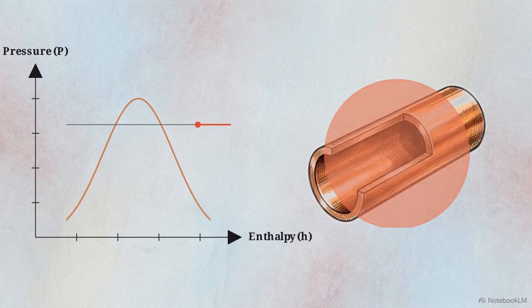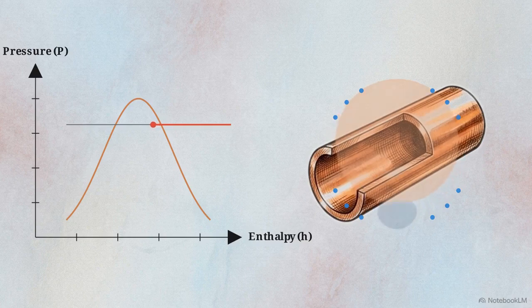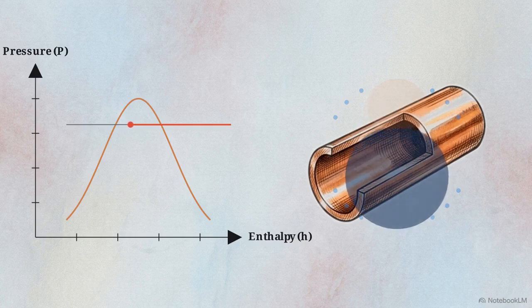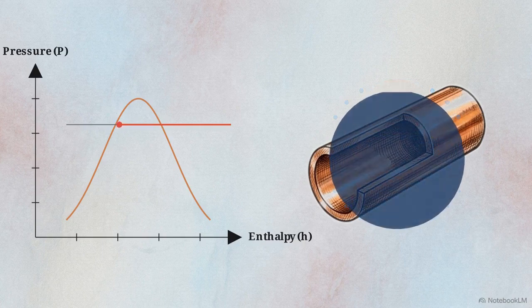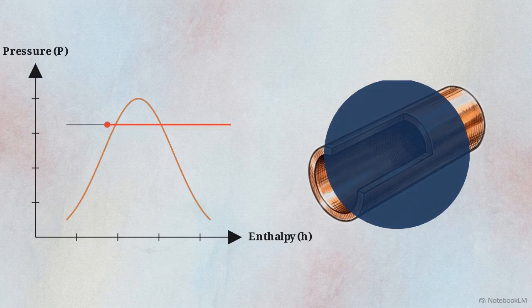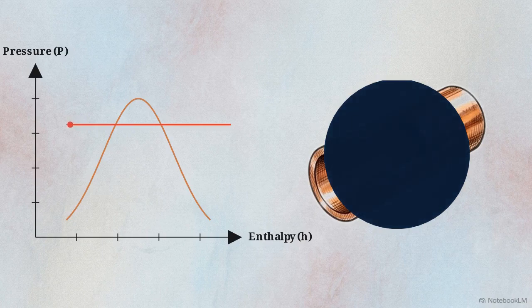The sensible heat drops rapidly as the vapor rejects energy, but the physical state of the refrigerant remains a gas. Step 2 brings the refrigerant into a saturated vapor state. We reach the exact temperature where the gas begins to yield, and liquid droplets first form on the inner walls of the pipe. Step 3 is the core phase change. The remaining latent heat is stripped away until the vapor undergoes full conversion into a liquid state. Step 4 completes the process through subcooling. We cool the liquid below its boiling point to ensure absolute stability before it leaves the condenser block.